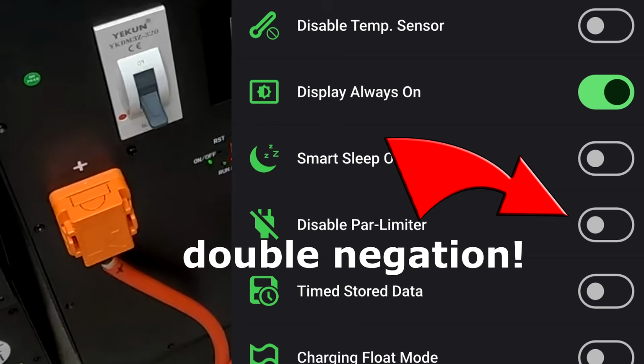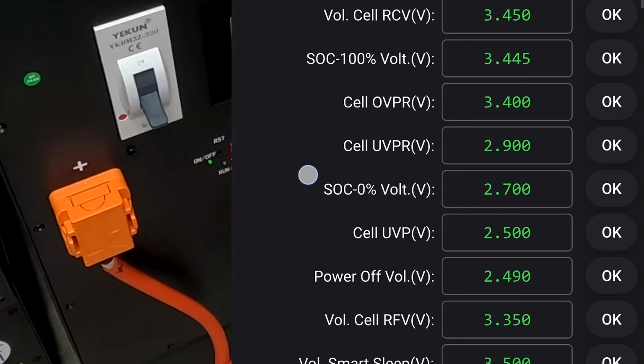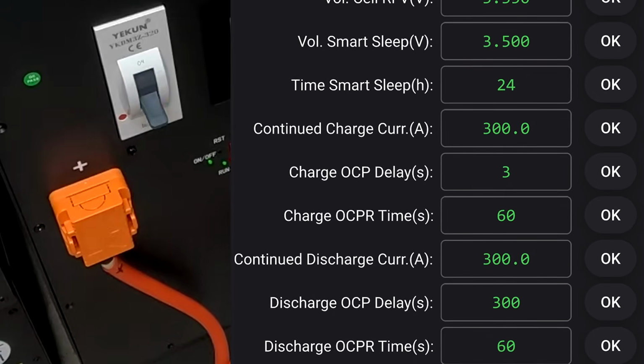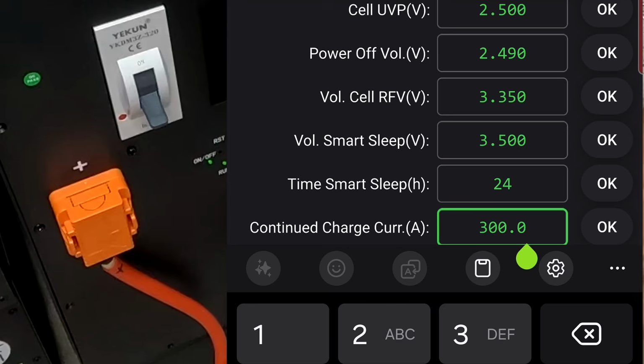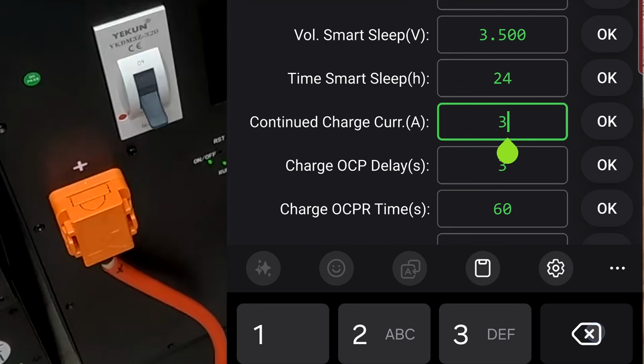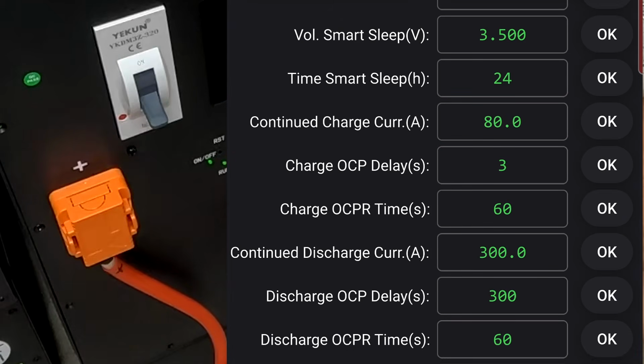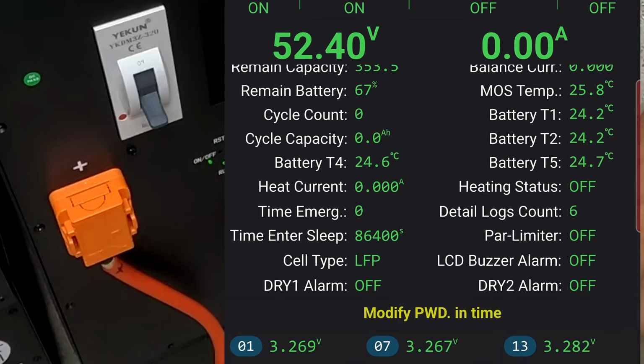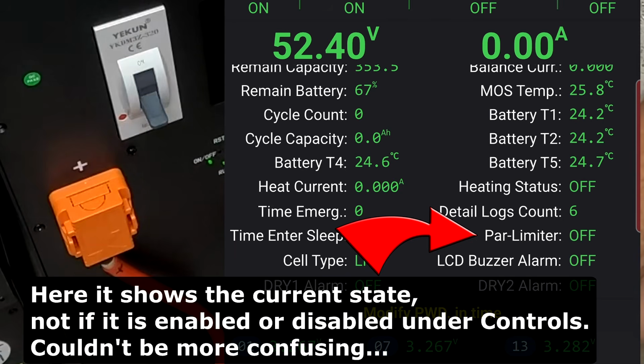Disable parallel limiter - we don't want to disable it, just make sure this one is turned on. And then we set the maximum charge current to, where is it? Continue charge 300 amps - see, this is a bit too much. So we set this one to 80 amps. If we go over 80 amps for 3 seconds, it should disconnect the charging, and then the parallel limiter, the current limiter, kicks in, and we should see a 10 amp current going into this battery.